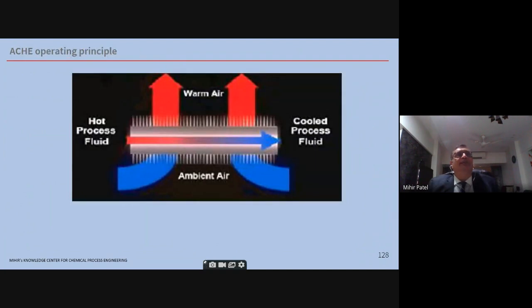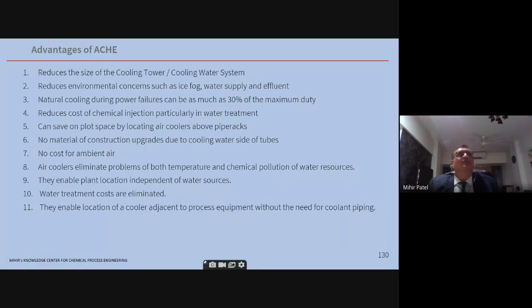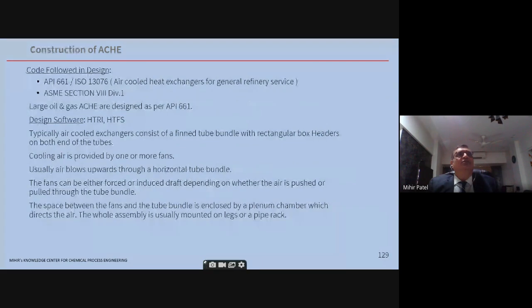So here is how it operates. Hot process fluid enters, air enters from the bottom, warm air goes out, and cool fluid goes out on the right. So, construction of ACHE. The code followed is API 661, ASME Section 8 Division 1, since it's pressurized on the header side, the tube headers. So most oil and gas ACHEs are designed as per API.